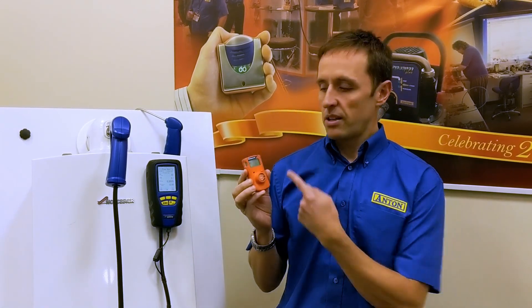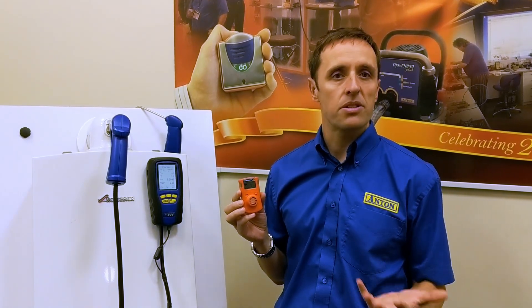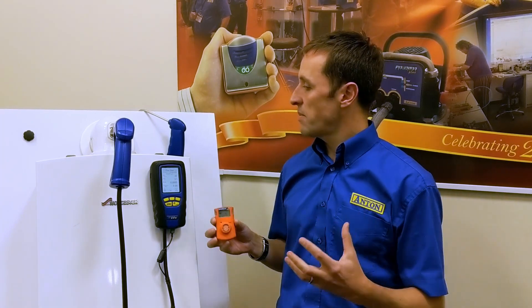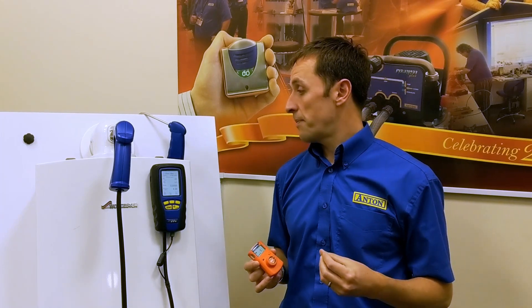A lot of people say I don't need one of these if the household has let me in — how unsafe can it be? Well, not every appliance is in the kitchen anymore; a lot are in the loft or a basement, a confined space. They might be getting low-level poisoning as the carbon monoxide travels down through the ceiling or up through the floorboards. But you could be going into that confined space, putting it into service mode, and getting a lot of carbon monoxide in a short space of time.